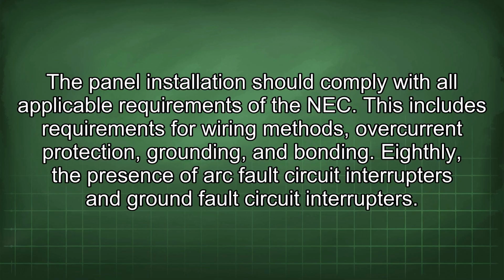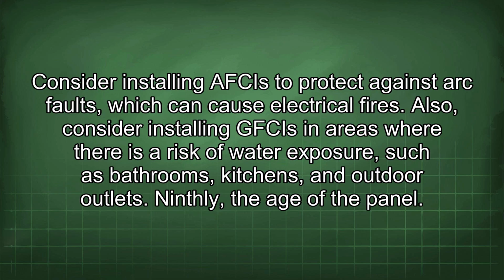Eighthly, the presence of arc fault circuit interrupters and ground fault circuit interrupters. Consider installing AFCIs to protect against arc faults, which can cause electrical fires. Also, consider installing GFCIs in areas where there is a risk of water exposure, such as bathrooms, kitchens, and outdoor outlets.